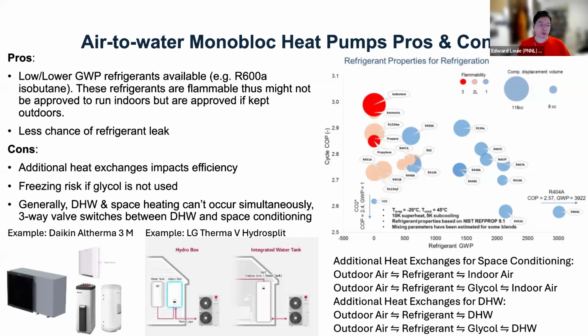One of the cons of a glycol system, if you look at the lower right-hand part of the slide, is that once you add glycol in the system, you have some additional heat exchange. Normally you go refrigerant to indoor air, but in a monoblock system, you go refrigerant to glycol and then glycol to indoor air. So that additional heat exchange step is not thermodynamically free. There is some efficiency loss as a result.